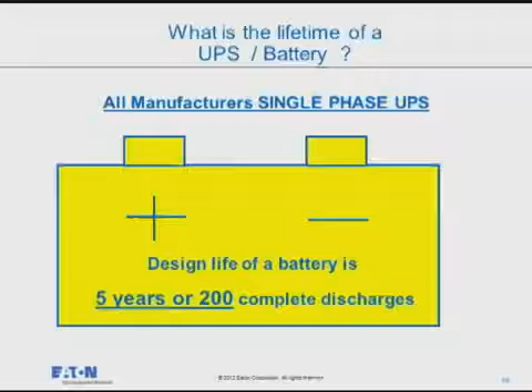When we look at the design life of a battery, typical applications have two. Single-phase UPSs, the small ones, look like motorcycle batteries, for lack of a better analogy. They're typically rated for a 5-year life or 200 complete discharges. 200 complete discharges uses up the battery through the whole charging process, and 5 years because there's a lifespan to the electrolyte within a battery. Larger 3-phase UPSs typically use a 10-year design life, still with 200 complete discharges, but the electrolyte will last a little longer. Now, even though it's a 10-year design life, typical experience has been 4 to 6 years out of that 10-year battery. Whole different discussion as to how that works, but again, typically 4 to 6 years.